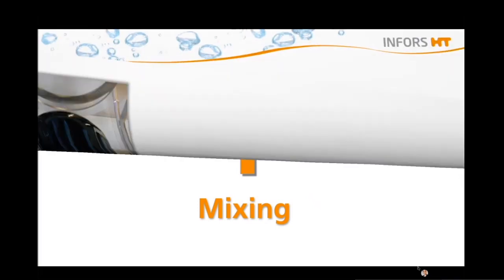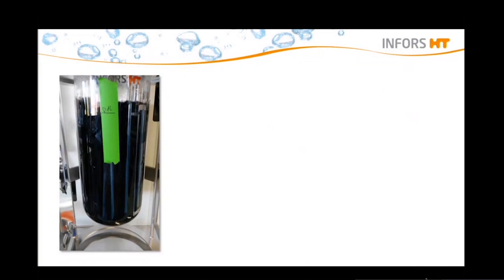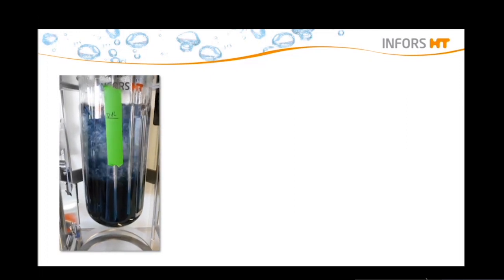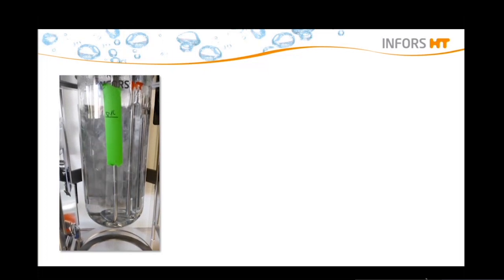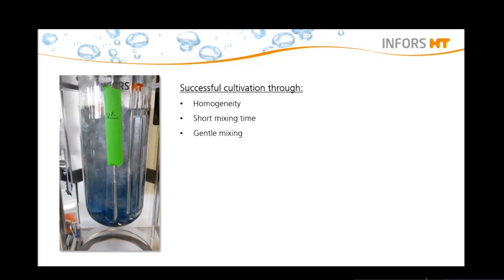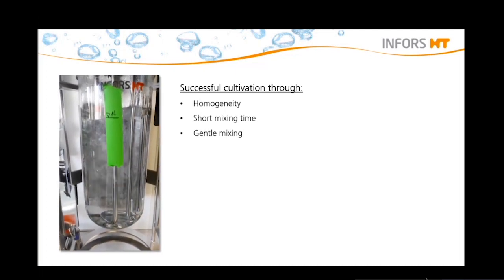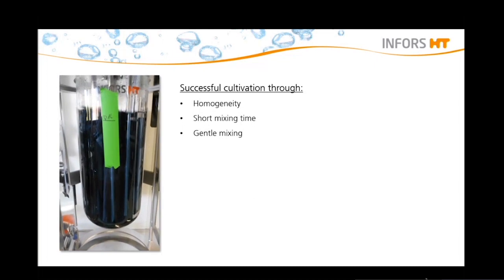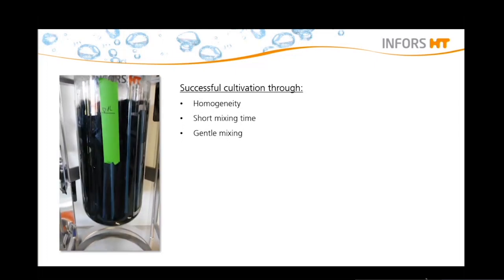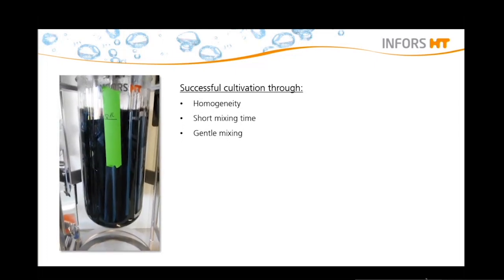As you can see here in this video, we took it to determine the mixing time of the Minifors 2 microbial version where we applied the discoloration method. As you can see, the media gets clear very fast, so we achieve homogeneous conditions within seconds. Insufficient mixing would result in pH and nutrient gradients, and that has been shown to dramatically influence cell growth and also antibody production. Everything clear so far? Yes, thanks, everything is clear.